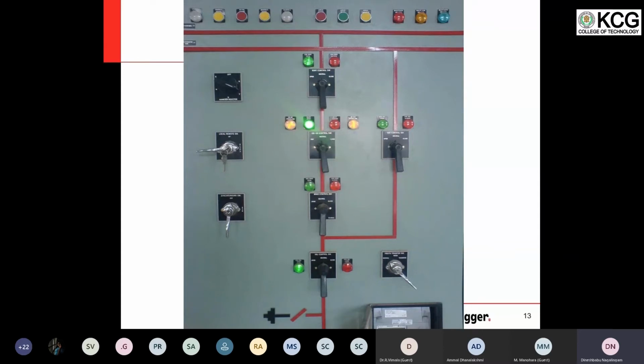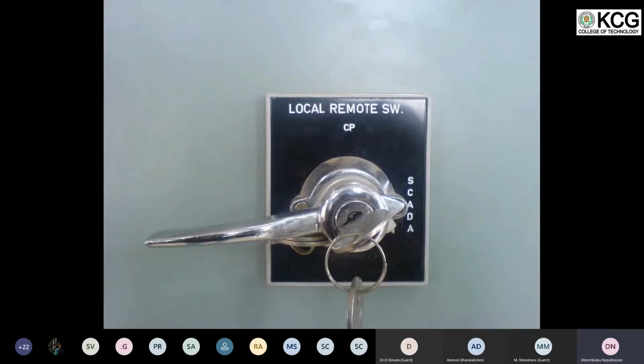So what they did was, they used a switch like this called the CP SCADA switch. That means when the switch is in SCADA position, only the operator from the remote location can operate. The local person cannot do any operation. When the switch is in CP position, control panel position, only the person standing in front of the panel can operate. No one from SCADA can operate.